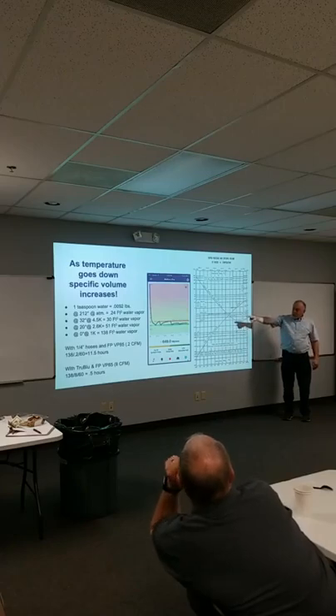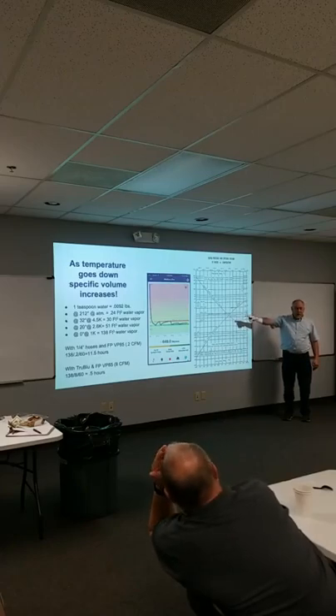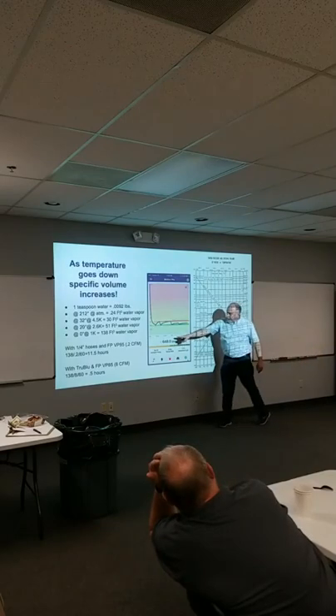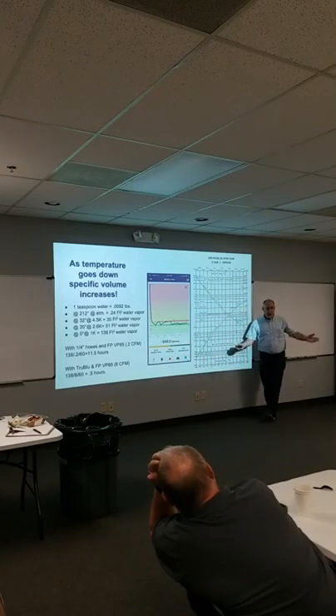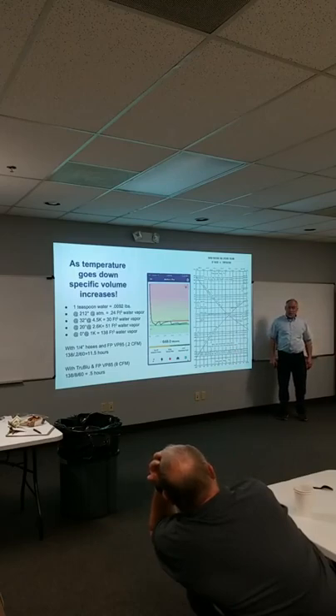Second time I pulled it down, it took longer than the first time. That meant I had some moisture. I removed some of the moisture in the system. Notice this is 15 minutes, 30 minutes, 45 minutes. Now we're not pulling that vacuum down in 7.5 minutes to below 100 microns, because the system's soaking wet. All right, this is what happens when you get on a wet system: all bets are off, because now what took you 7 minutes is going to take you maybe 7 hours, maybe 7 days. Longest evacuation I had was probably a little over 30 days that I was evacuating.